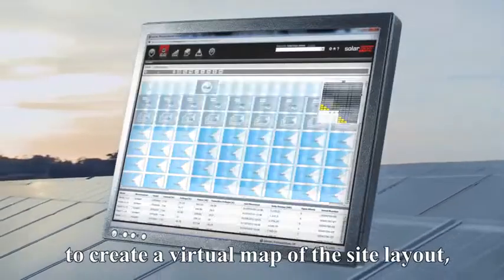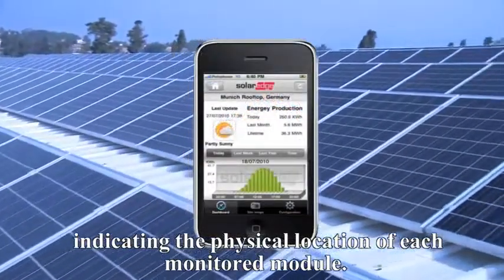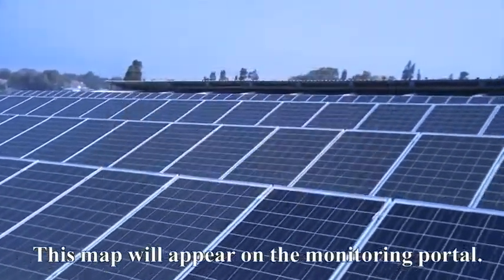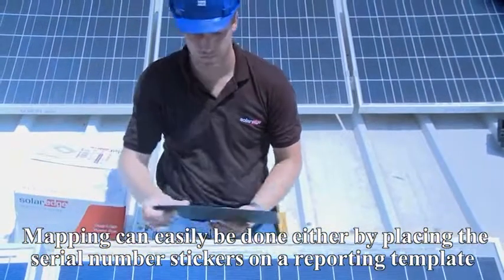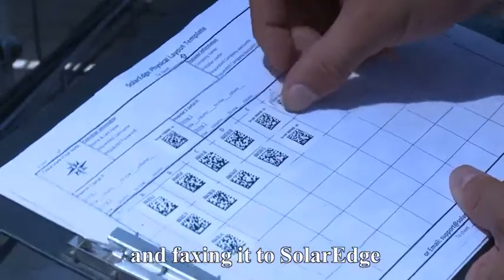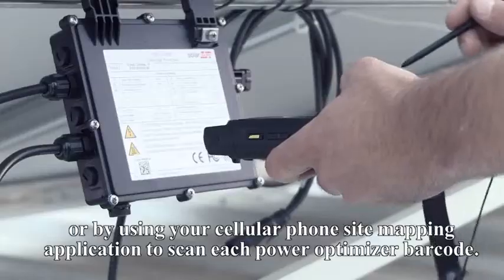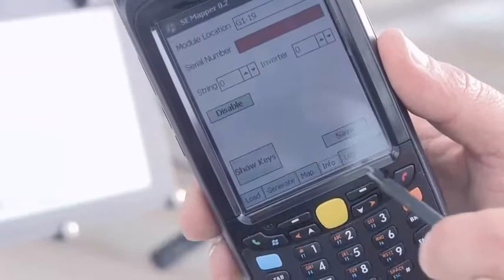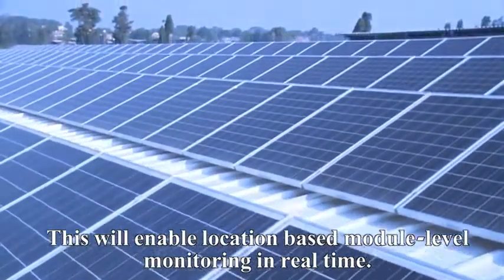To take full advantage of your module level monitoring, now is the best time to create a virtual map of the site layout, indicating the physical location of each monitored module. This map will appear on the monitoring portal. Mapping can easily be done either by placing the serial number stickers on a reporting template and faxing it to SolarEdge, or by using your cellular phone site mapping application to scan each power optimizer barcode. This will enable location-based module level monitoring in real time.